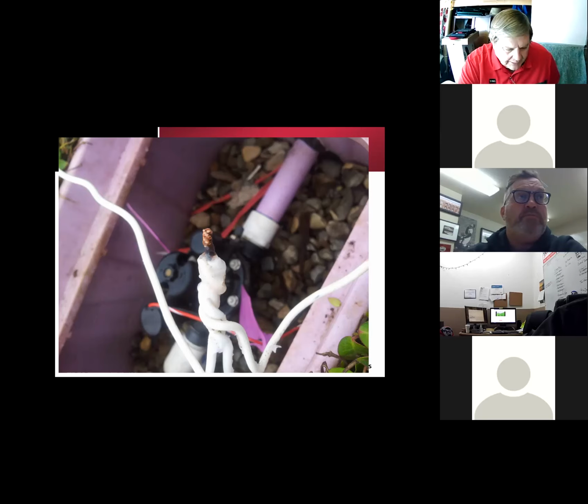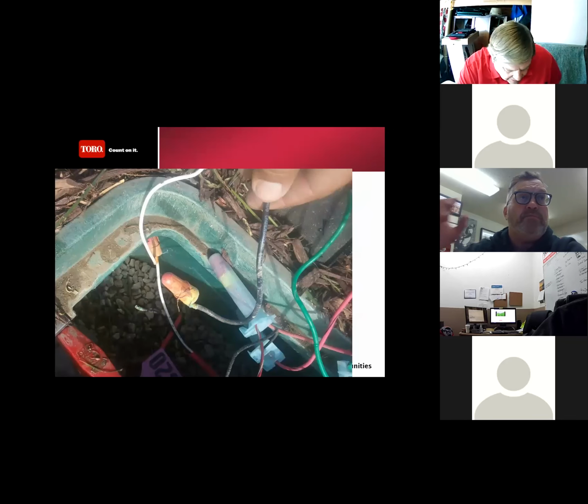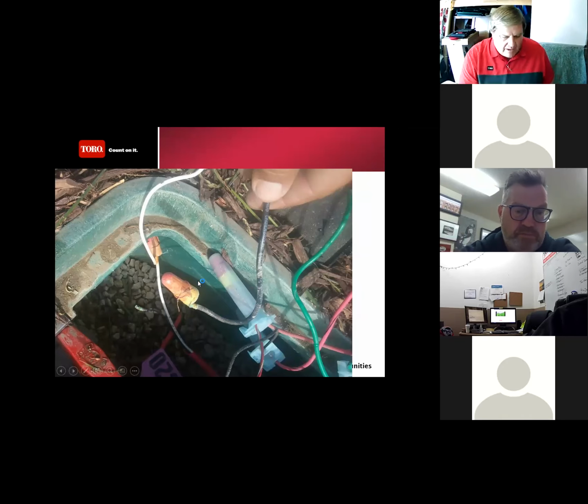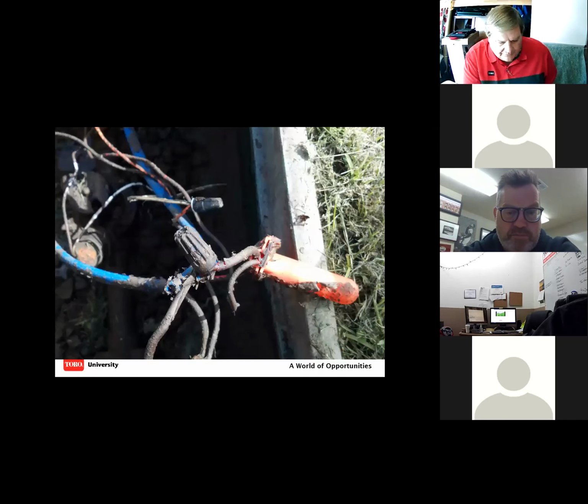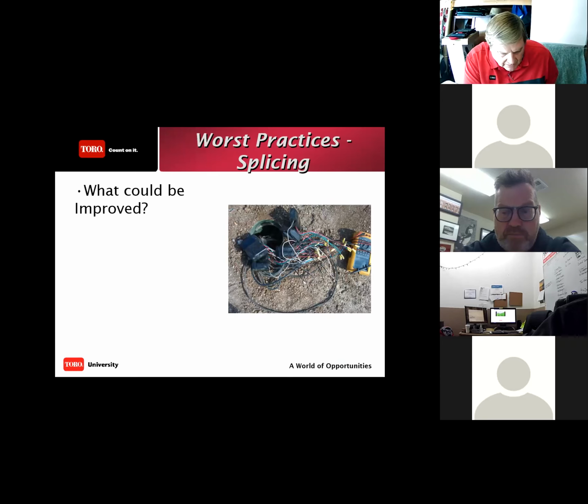Be very careful. Look at this here. There's my wire nut. The wire's corrosion right there is so bad. The wire connection here just came right out. It just broke right off. That is not good in any way, safe or otherwise. But note, on this one he got the wire all the way to the bottom of the tube. So very important. I don't even know what to say about this one. What a smorgasbord, a buffet line of different connections. Be careful with what you're working with out there.